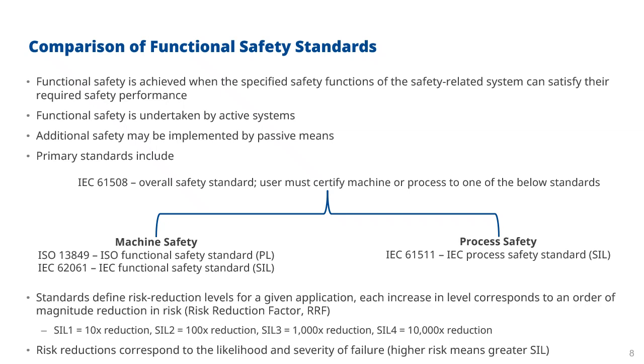What I've seen is a lot of people have moved from SIL 3 to SIL 2 by adopting mitigating factors. So for example, if you've got an oil rig, if it's a manned oil rig, then you might find that you need SIL 3 reduction because you've got to protect all those operators. If you can move to unmanned operations, now you don't have any people or as many people to worry about, so you might be able to move down to SIL 2. So that's a good example of how you can reduce the risk factor by removing people from the equation and then reducing the amount of safety you require.